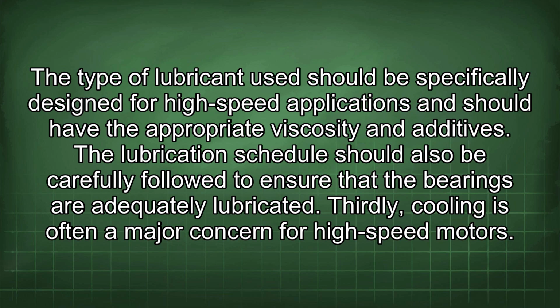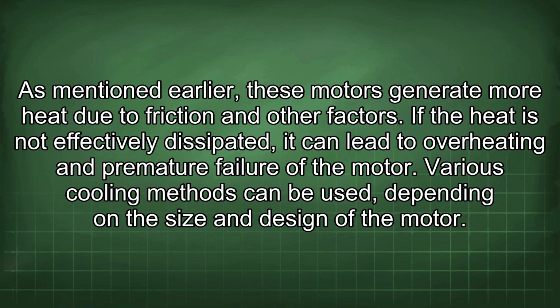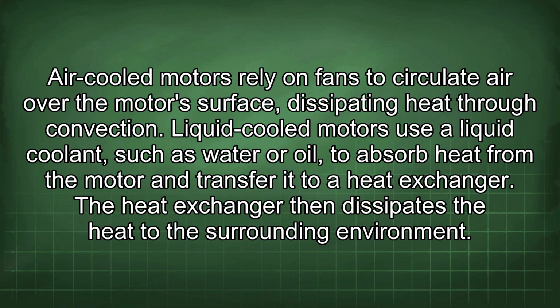Thirdly, cooling is often a major concern for high-speed motors. As mentioned earlier, these motors generate more heat due to friction and other factors. If the heat is not effectively dissipated, it can lead to overheating and premature failure of the motor. Various cooling methods can be used depending on the size and design of the motor. Air-cooled motors rely on fans to circulate air over the motor's surface, dissipating heat through convection. Liquid-cooled motors use a liquid coolant, such as water or oil, to absorb heat from the motor and transfer it to a heat exchanger. The heat exchanger then dissipates the heat to the surrounding environment.